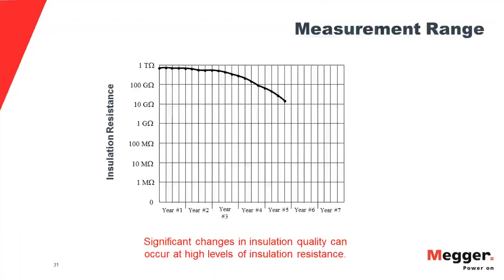One of the reasons here would be what we show you on this graph. If you were keeping maintenance records, and note, if you had a tester that only went to 1 or 2 gigohms, you wouldn't be able to construct a graph like this. And this is kind of a distant early warning. What this is telling you in this particular case is that insulation resistance is dropping rather rapidly. And it's still very high, and a single test would make it look like, oh, this is good. You wouldn't have any problem determining whether it's good or bad, but you wouldn't have any idea of the rate of change. And what may be happening here, if this was a motor in an industrial environment, let's say, there could be moisture getting from a nearby process, and all you may need to do is put up some sort of a guard around it, and you could stop this. Okay.